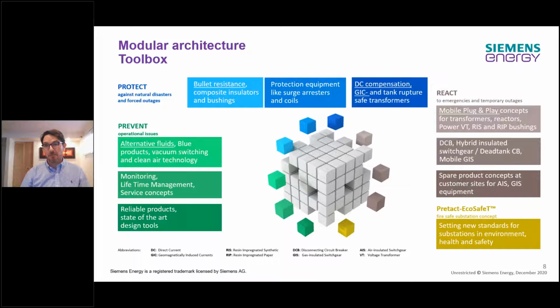Alternative fluids could also come into play, especially ester fluids, maybe because of the need for increased fire safety. In a contingency situation, you might need to consider installation in an area with reduced fire clearances or reduced fire suppression capabilities, or maybe for environmental reasons, a biodegradable fluid facilitates deployment during contingency.